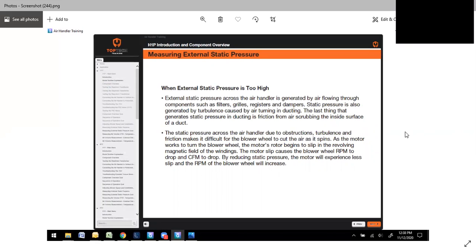When external static pressure is too high, the external static pressure across the air handler is generated by air flowing through components such as grills, filters, registers, dampers. Static pressure is also due to turbulence caused by air turning in ducts that turn right off the top of the air handler. The last thing that generates static pressure is friction from air scrubbing inside the surfaces of ducting, flex duct, anything that can cause restrictions.